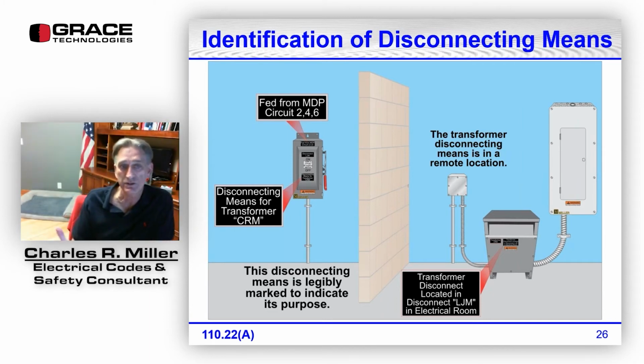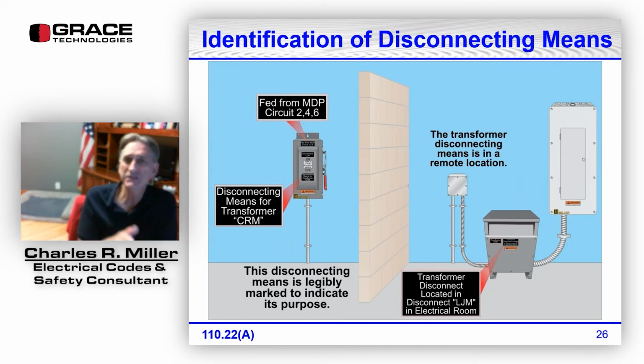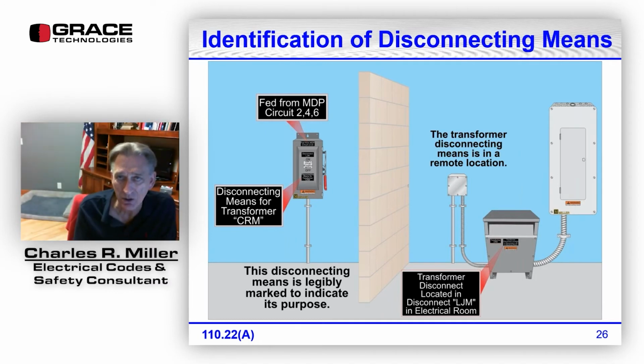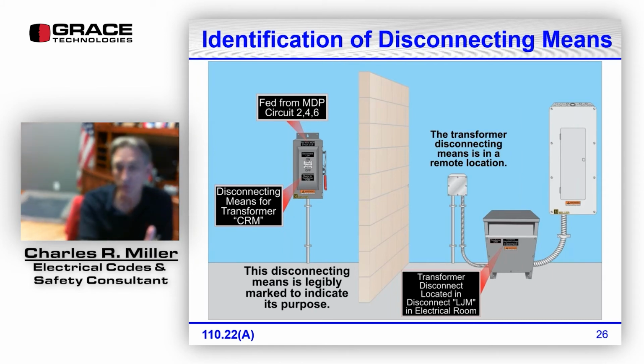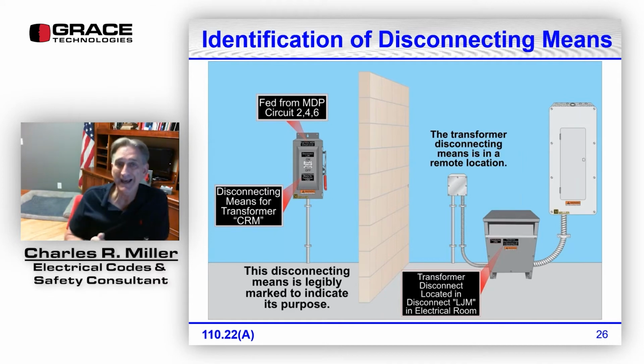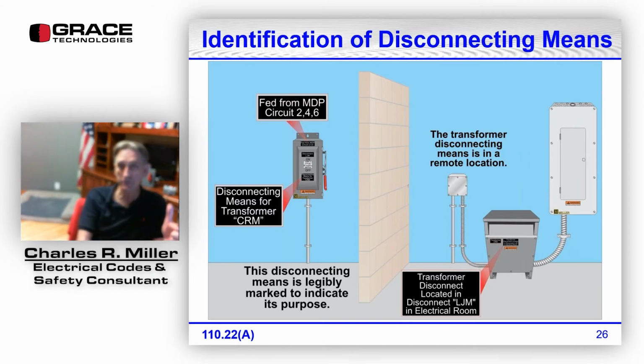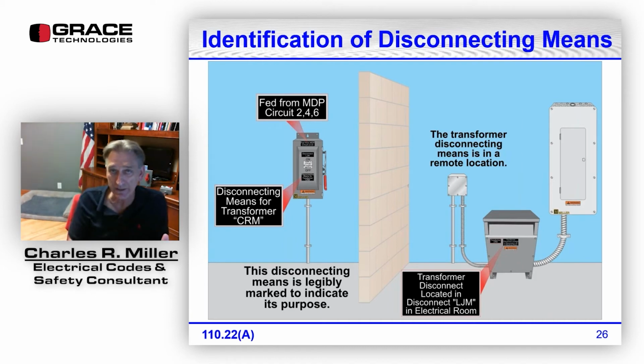All right, so in Article 100 of the National Electrical Code, I mentioned that if the disconnecting means is not within sight. Within sight is defined in Article 100. Within sight, or within sight of, within sight from, it means that the disconnecting means has to be visible from the device you're turning on or off, and the maximum distance is 50 feet that they can be apart from each other. So it has to be visible and no more than 50 feet away, the disconnecting means.